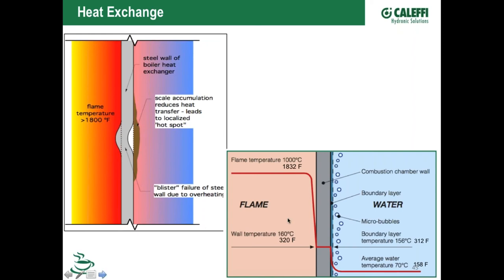This gives you an example of the temperatures you can expect to see here. This also shows a good example of when you heat water, you're going to drive little micro bubbles out of solution. If you put a pan on your stove tonight and fill it with water and turn the burner on, you'd see little bubbles rise up out of that pan. That's the air entrained in the fluid being driven out as you increase the temperature. That's why we always want a good air separator, a micro bubble type air separator like a Discal, right at the boiler.